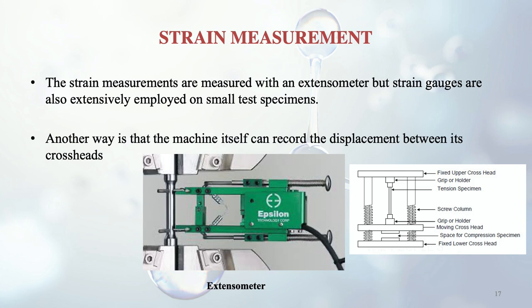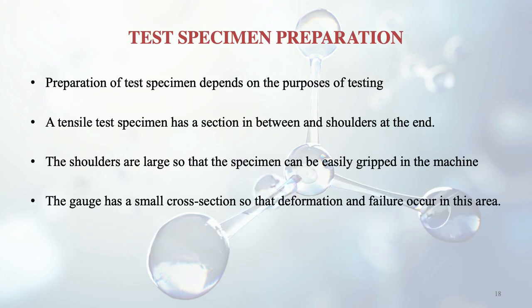Before starting the simple tension test, the test specimen must be prepared. A tensile test specimen has a middle section and shoulders at the ends — similar to a dumbbell, where the middle portion is thinner and the ends have a larger diameter. The shoulders allow the specimen to be easily gripped in the machine, while the smaller cross-section in the gauge region ensures that deformation and failure occur there.